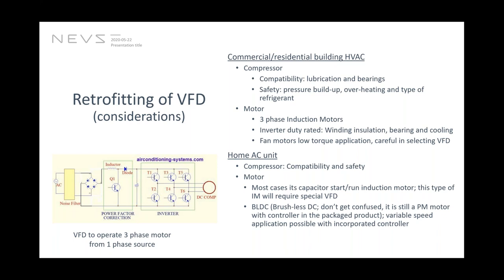And then with regard to the retrofit, what type of motor is being used? In big commercial or residential buildings with central HVAC, if it is an old system, they will usually be using a three-phase induction motor as a plug and play line start motor. If it is a three-phase motor, then obviously a VFD can be implemented, but the things to be considered are, again, as I discussed in my previous slide, the winding insulation, dV/dt of the winding insulation, bearing currents, and cooling.